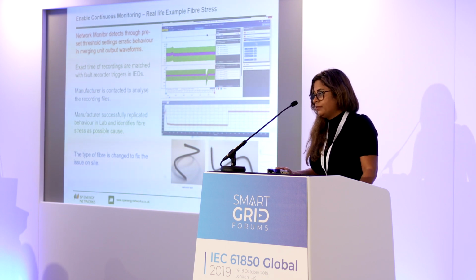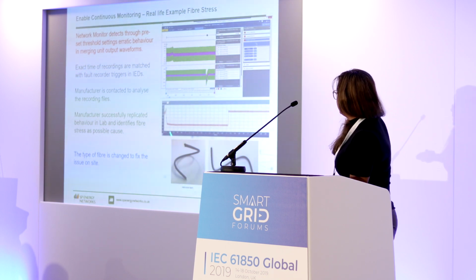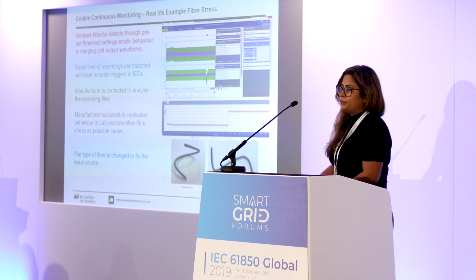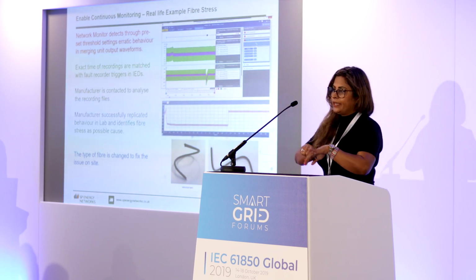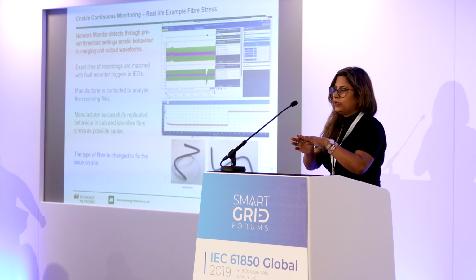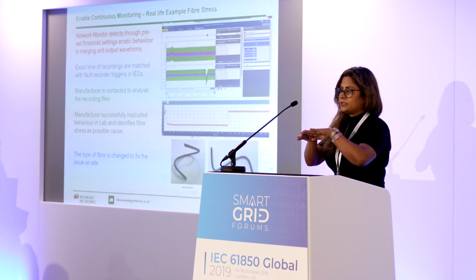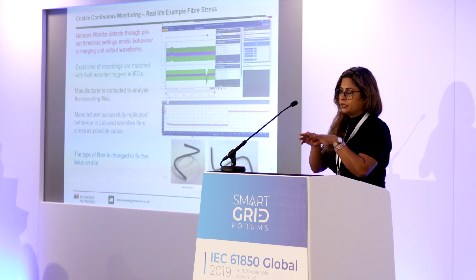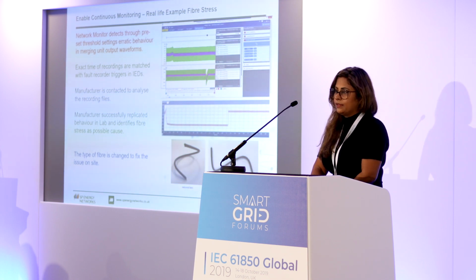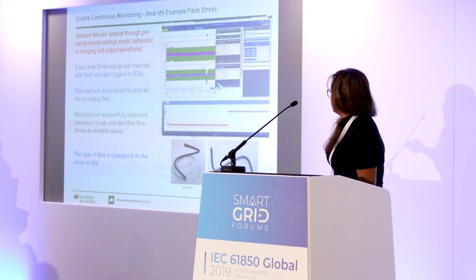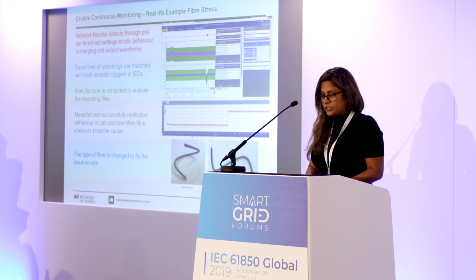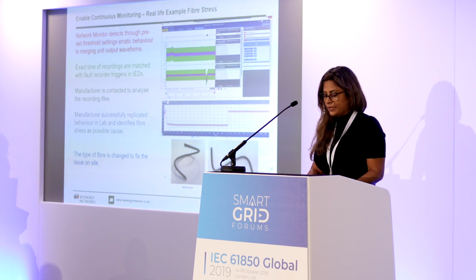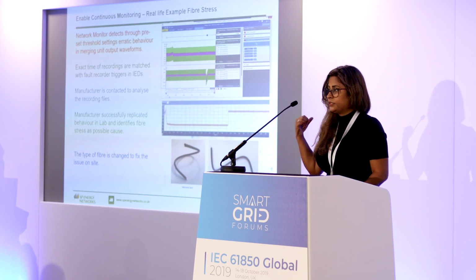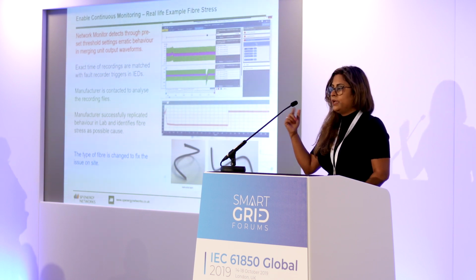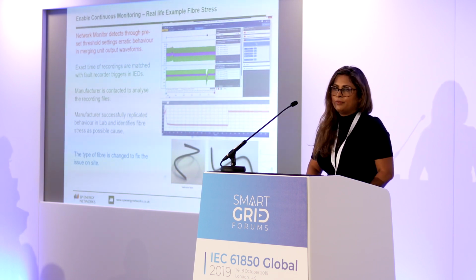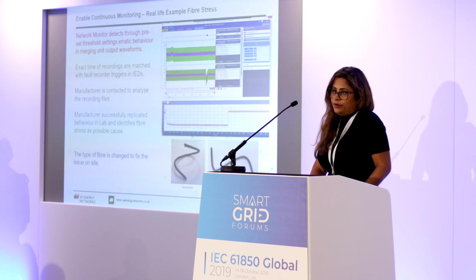And of course, the vendor could identify the issue and replicate it in the lab, and we found out the problem was that bending an armored cable causes physical stress. When this stress releases itself because of variation in weather conditions or temperature, it causes a deviation in the light signal. And that's what was causing this kind of behavior. Of course, we still don't have a proper installation because it's too late, but we replaced the armored cables with flexible fibers in conduits so they don't have that kind of mechanical strain, and the behavior was resolved.